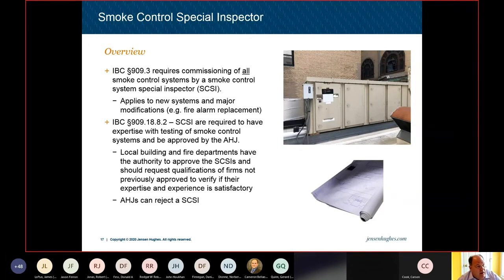So the IBC, basically everywhere in the country, requires commissioning of all smoke control systems by a smoke control special inspector. And there are qualifications that go along with that. The smoke control special inspectors are required to have expertise with testing of smoke control systems. And as we talked about, the smoke control system is really an integration of a bunch of systems, including the fire alarm system. So that's an important thing to note.